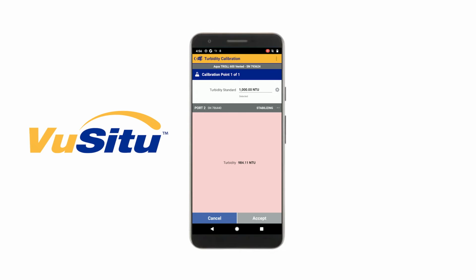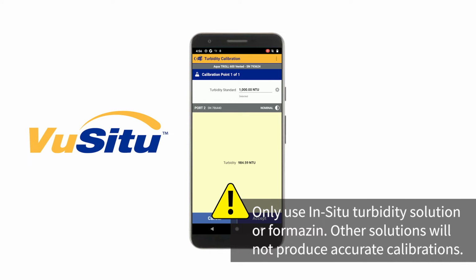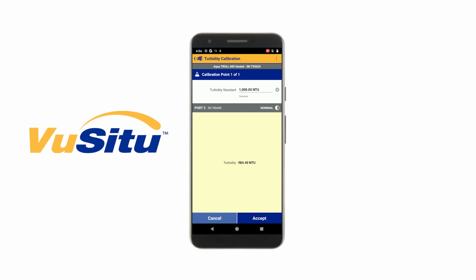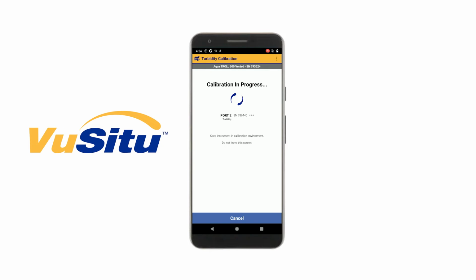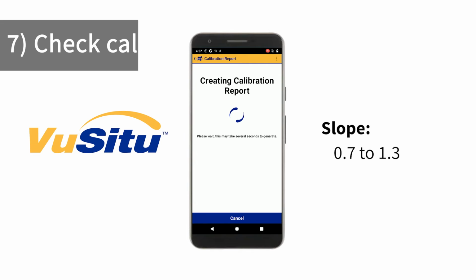It's very important to only use In-Situ turbidity solution or formazine. Polymer bead standards from other manufacturers will not produce accurate calibration results. When the readings have stabilized, tap Accept. After calibration, check the calibration report and confirm that the slope is within the acceptable range on the screen.